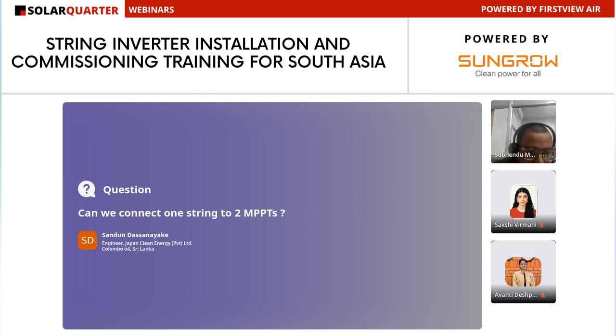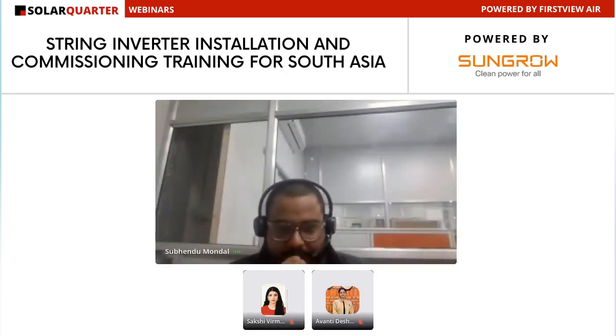Can we connect one string to two MPPTs? We want to ask, can we connect two strings in one MPPT, or one string to two MPPTs? We can connect two strings using a Y connector in a single MPPT. I think there is a typing mistake. It will be two strings in one MPPT, I think you want to know. Yes, we can connect two strings in a single MPPT.